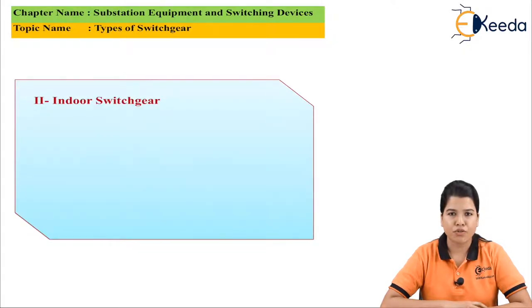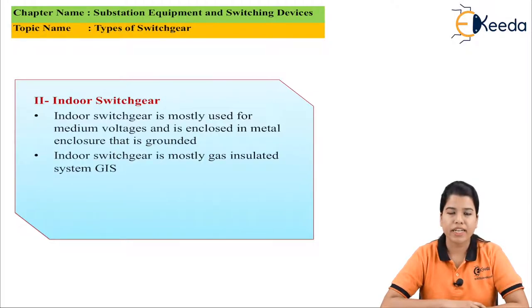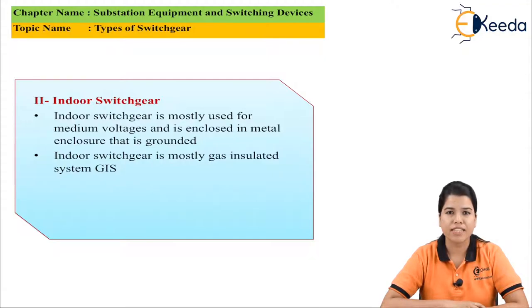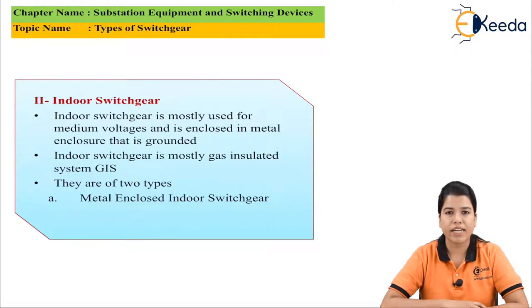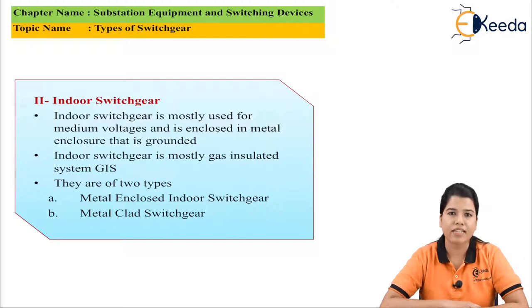The second type is indoor switchgear. Indoor switchgear is mostly used for medium voltage applications and it is enclosed in a metal enclosure, which is mostly grounded. Indoor switchgear basically consists of a gas insulated system. It is of two types: metal enclosed indoor switchgear and metal clad indoor switchgear. The gas insulated system uses SF6 gas, that is sulfur hexafluoride, which has very superior dielectric properties.